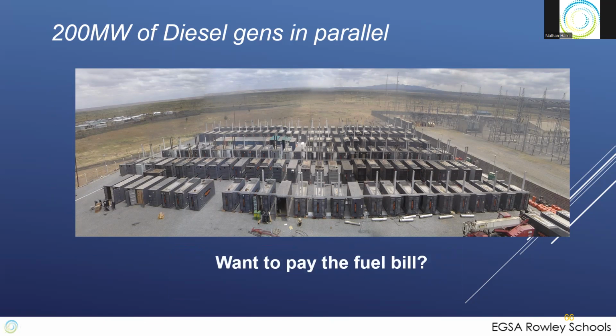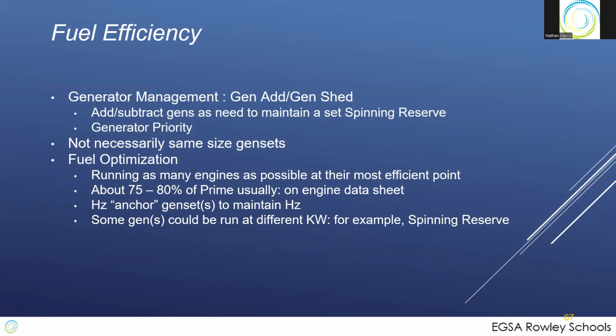so we talk carefully about fuel efficiency, and we have that in the form of generator management. We use GenShed and GenAdd to run a certain minimum number of generators to achieve this level of fuel efficiency. We don't necessarily have to have the same size gens, but we also run fuel optimization. An engine-generator combination is most efficient not at its nameplate 100% value, but somewhere around 75 to 80% of the full nameplate value. Of course, we're not talking total power, we're talking efficiency: a fuel in, power out calculation, right? And so some gens can actually run at different values.